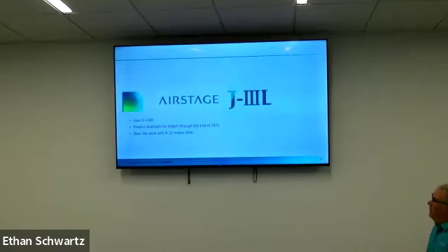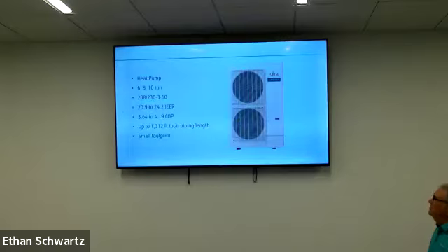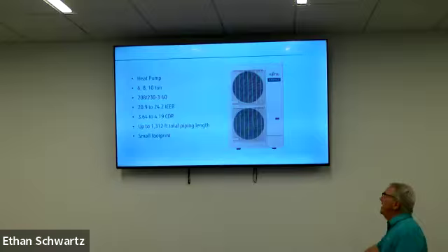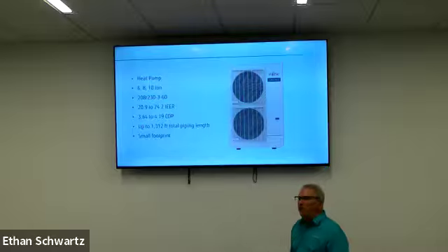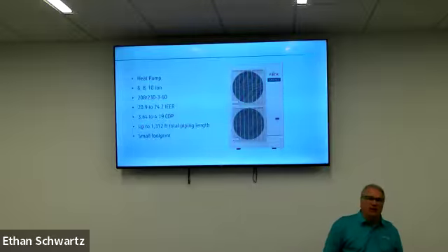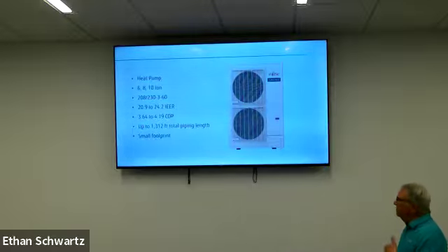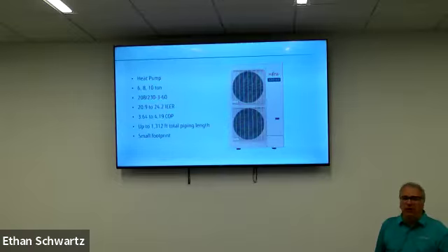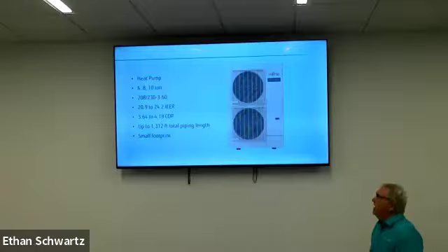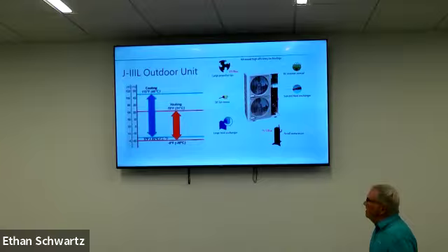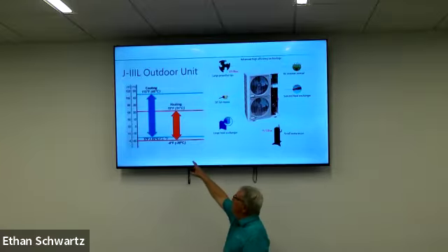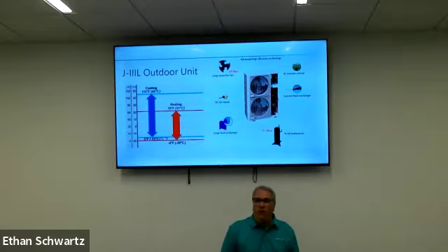J3L is just up from the J series. It is 3-phase only, available in 6, 8, and 10 ton, and currently R410A, but that 10 ton will do up to 30 indoor units. So as far as a school, that might be a good choice, a church, something like that. The only thing is, it does have a rating to -4.